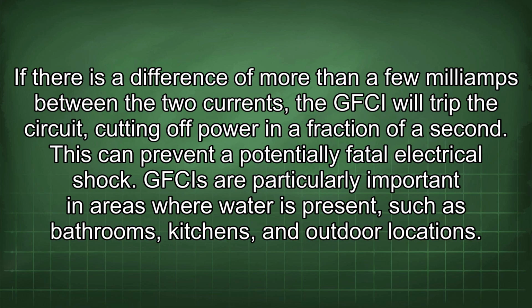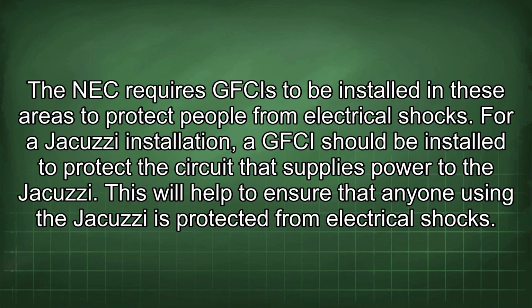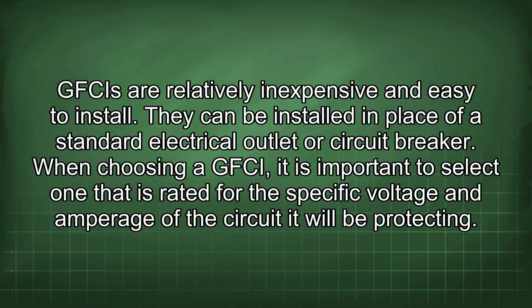GFCIs are particularly important in areas where water is present, such as bathrooms, kitchens, and outdoor locations. The NEC requires GFCIs to be installed in these areas to protect people from electrical shocks. For a jacuzzi installation, a GFCI should be installed to protect the circuit that supplies power to the jacuzzi. This will help to ensure that anyone using the jacuzzi is protected from electrical shocks. GFCIs are relatively inexpensive and easy to install. They can be installed in place of a standard electrical outlet or circuit breaker.